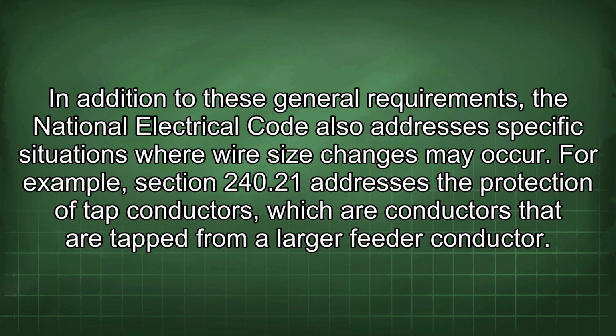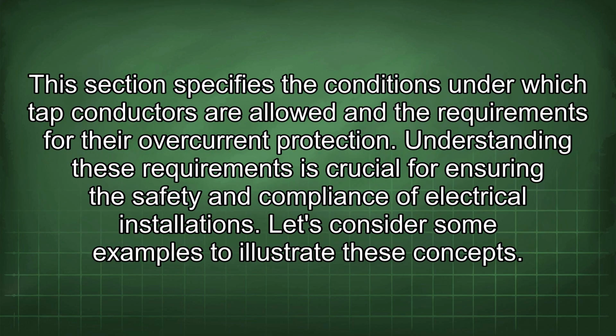In addition to these general requirements, the National Electrical Code also addresses specific situations where wire size changes may occur. For example, Section 240.21 addresses the protection of tap conductors, which are conductors that are tapped from a larger feeder conductor. This section specifies the conditions under which tap conductors are allowed and the requirements for their overcurrent protection. Understanding these requirements is crucial for ensuring the safety and compliance of electrical installations. Let's consider some examples to illustrate these concepts.